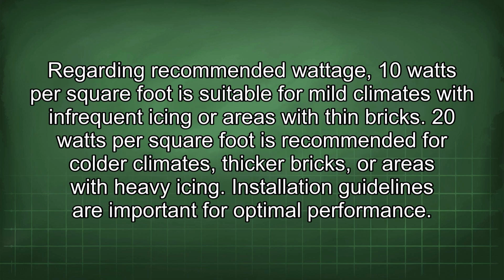Regarding recommended wattage, 10 watts per square foot is suitable for mild climates with infrequent icing or areas with thin bricks. 20 watts per square foot is recommended for colder climates, thicker bricks, or areas with heavy icing.